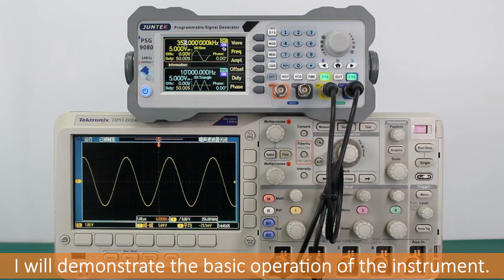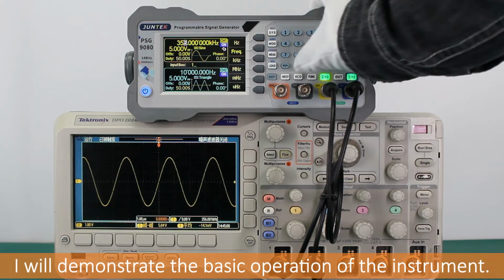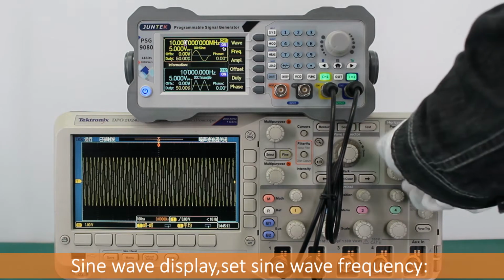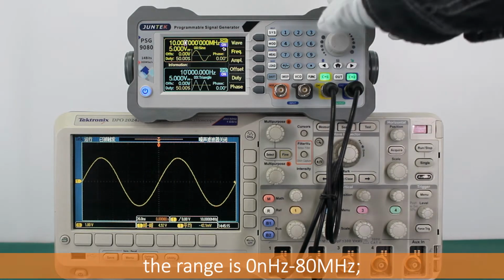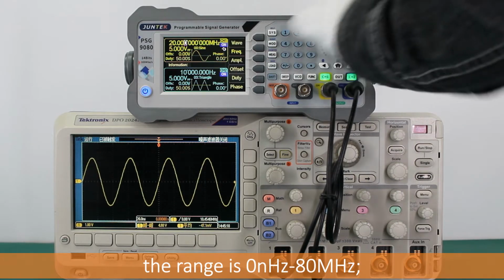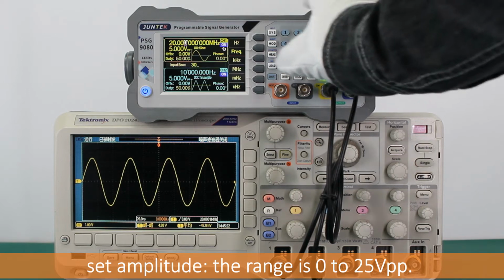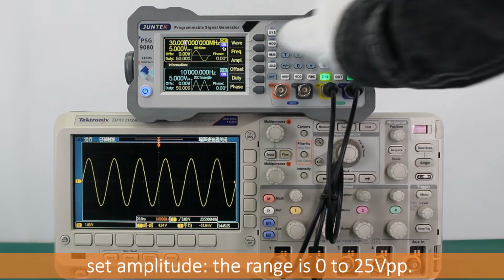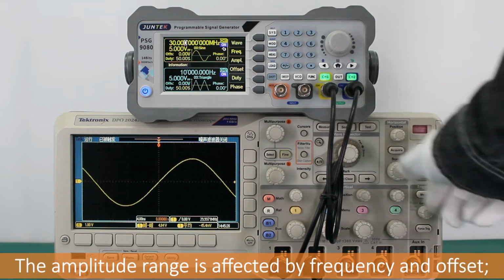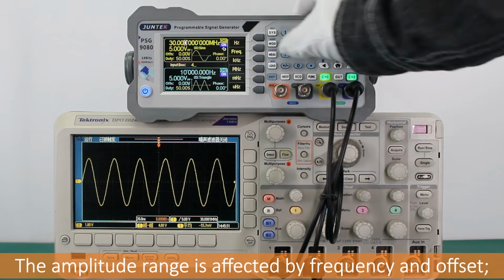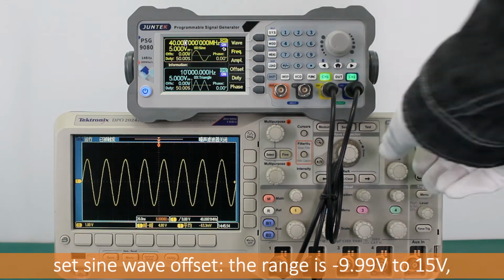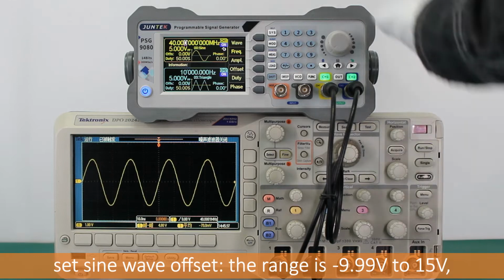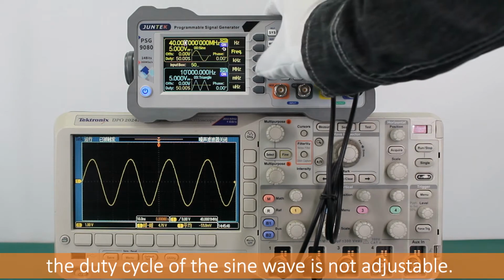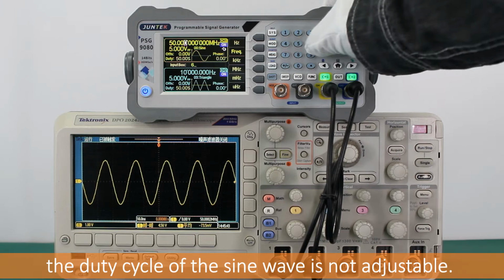Next, I will demonstrate the basic operation of the instrument. Sine wave display. Set sine wave frequency, the range is 0 Hz to 80 MHz, set amplitude, the range is 0 to 25 VPP. The amplitude range is affected by frequency and offset. Set sine wave offset, the range is -9.99 V to 15 V, the duty cycle of the sine wave is not adjustable.